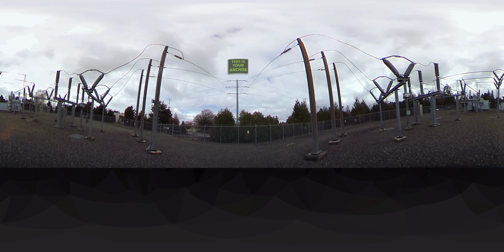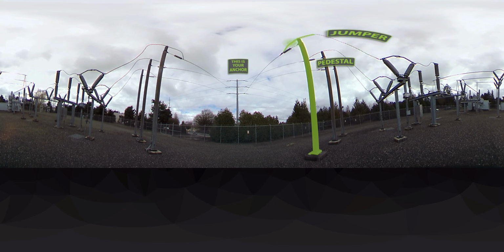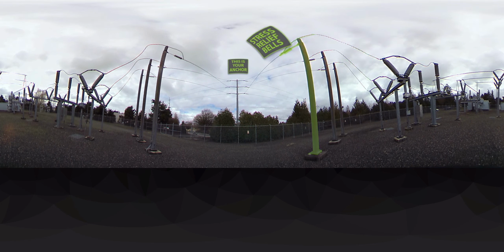Move your camera to the right and note how the 115 kV lines drop from the monopole into the substation. The lines connect to pedestals, and on top of each of these tall pedestals, the power coming in goes through what's called a jumper. The jumper acts as a bridge between the line and the substation. Right near the jumper, you will also notice what are called stress relief bells, commonly called bushings. These stress relief bells are ceramic insulators that help with the pressure from the weight of the cable connecting to the pedestals. Notice there are three lines, one for each phase of our three-phase power.